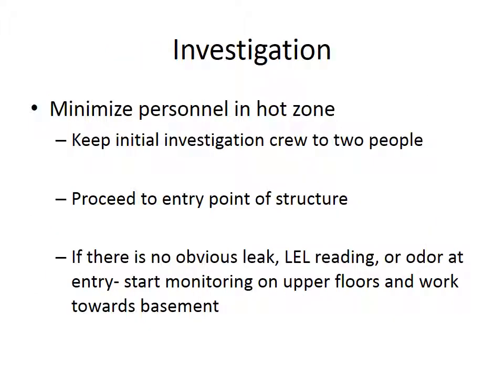The investigation: we want to minimize personnel in the hot zone. Ideally, try to keep the initial investigation crew to 2 people. The investigation crew, with the meter already on, is proceeding to the point of entry to the structure. And if there's no obvious leak or LEL reading or odor at the entry point, we want you to try to monitor going on the upper floors and work your way towards the basement. That really should be a goal for any type of structural investigation, to start up high and work down. Because why?